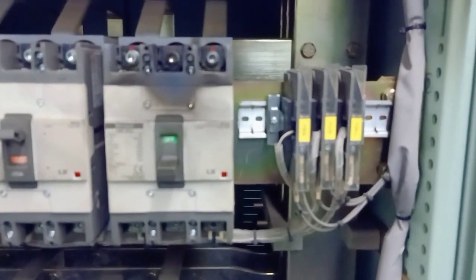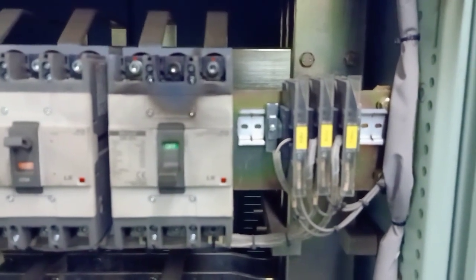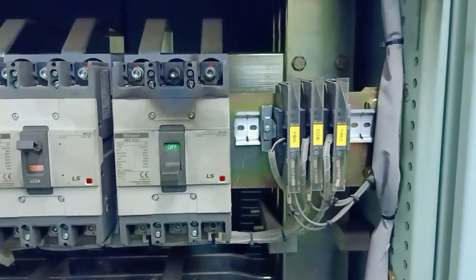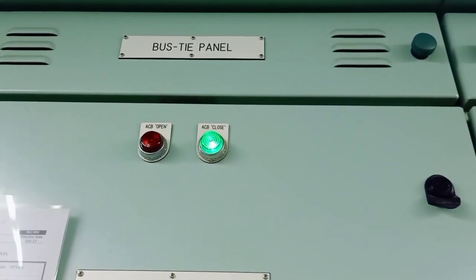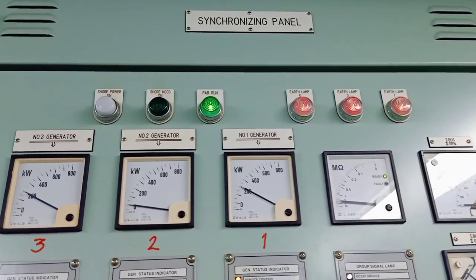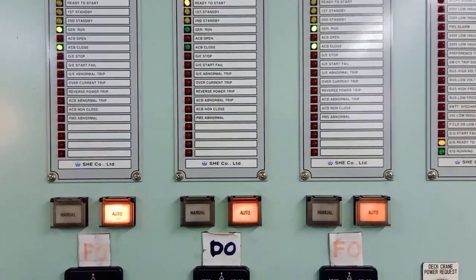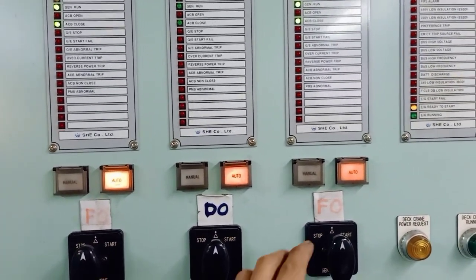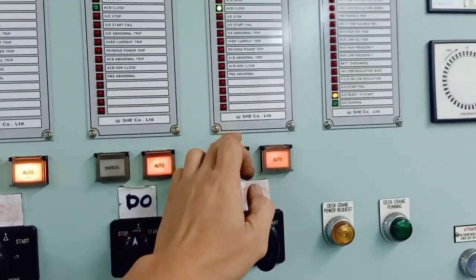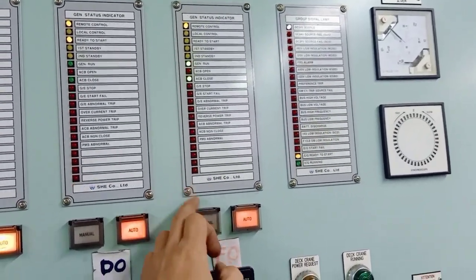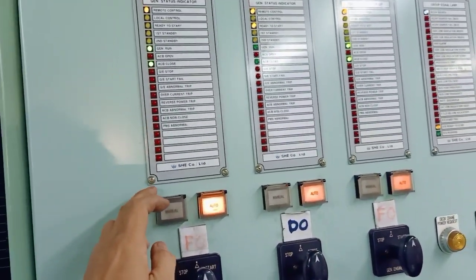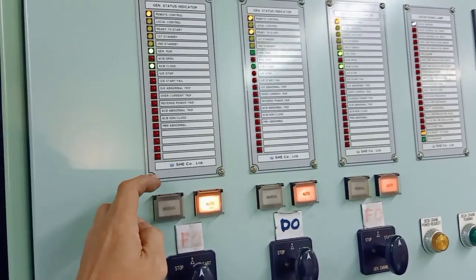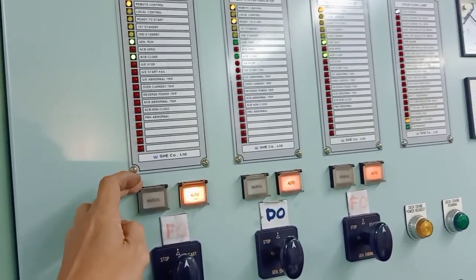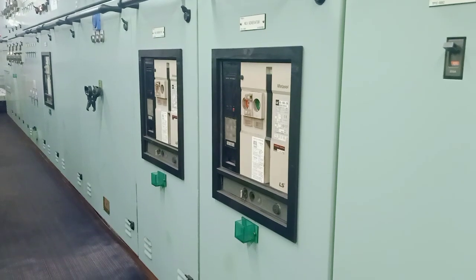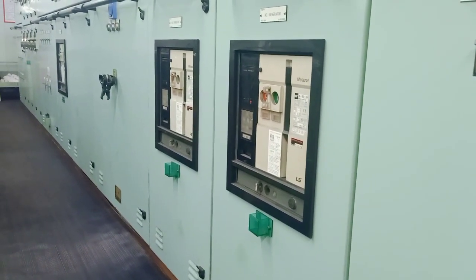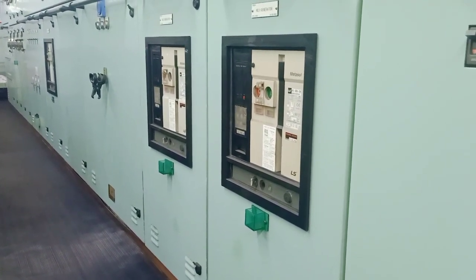To proceed with the replacement of this circuit breaker from the main switchboard, we need to black out to isolate from this line side. This is our bus tie panel board. This is our synchronizing panel board. To proceed with the blackout from the main switchboard, we need to shut off this circuit breaker. Also, on this other side, generator number 3, we need to shut off these two to proceed with the replacement of our circuit breaker, since it is a live circuit from the bus bar.